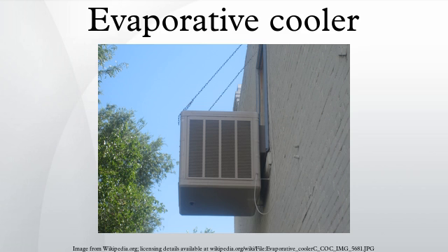Vapor compression refrigeration uses evaporative cooling, but the evaporated vapor is within a sealed system, and is then compressed ready to evaporate again, using energy to do so. A simple evaporative cooler's water is evaporated into the environment, and not recovered. In an interior space cooling unit, the evaporated water is introduced in the space along with the now cooled air. In an evaporative tower, the evaporated water is carried off in the airflow exhaust.